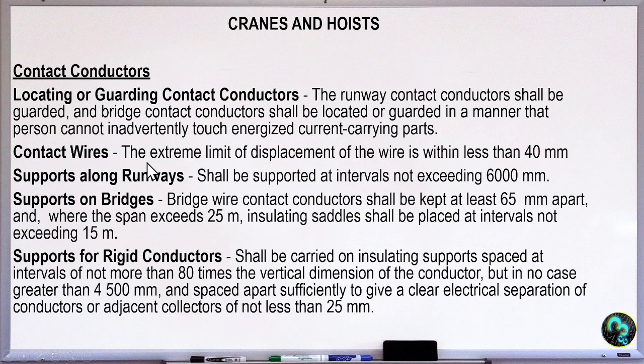The contact wire, so that is the extreme limit of displacement of wire, is within less than 40 mm. So, yung pinaka extreme na part or pinaka end ng wire is yung kanyang sobra is 40 mm. Support along runway shall be supported at intervals not exceeding 6000 mm.